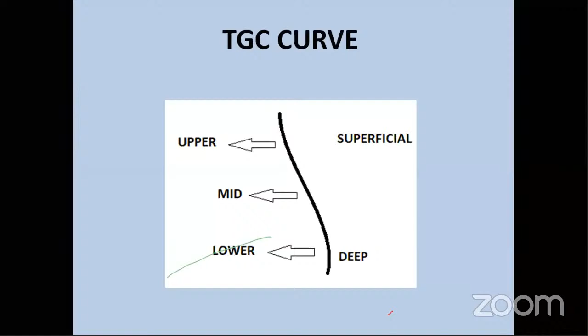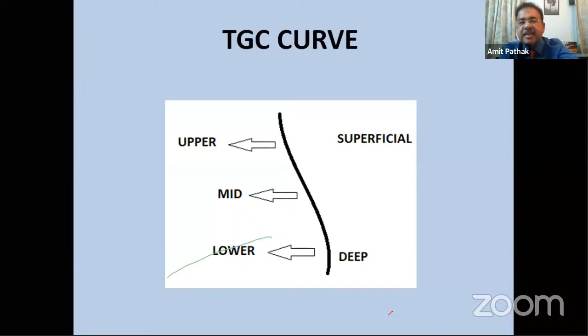So what you do is you use this TGC curve. In this, the upper knobs you turn towards the darker side and the lower knobs you turn towards the whiter side, and make the whole image symmetrical. You make the deeper parts whiter and the superficial parts less white, so that even though the ultrasound intensity coming in from the surface and the deep is different, the image is smooth and similar.